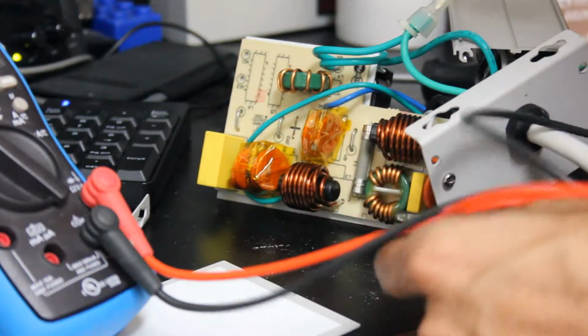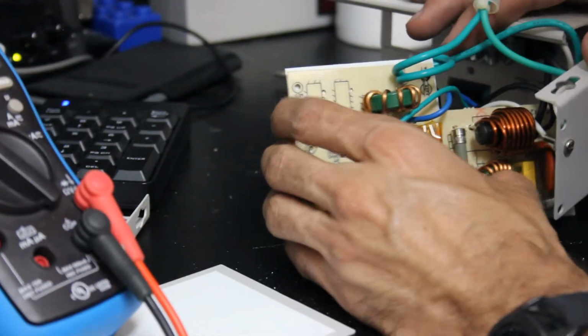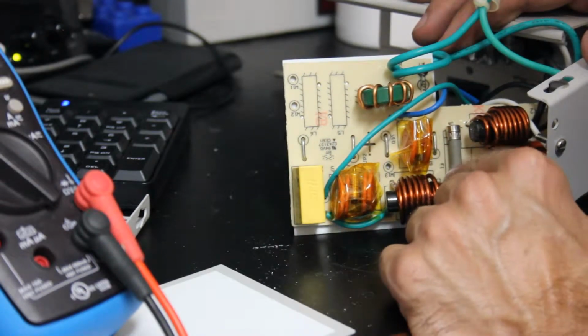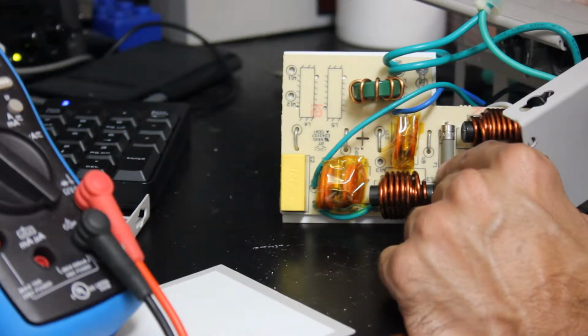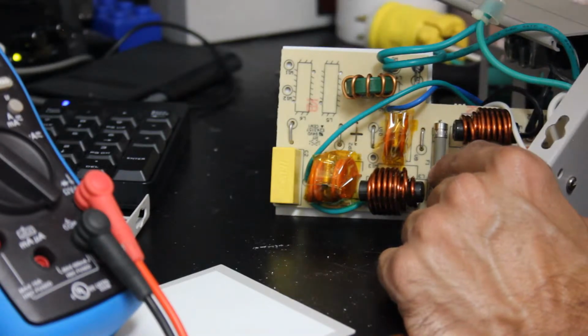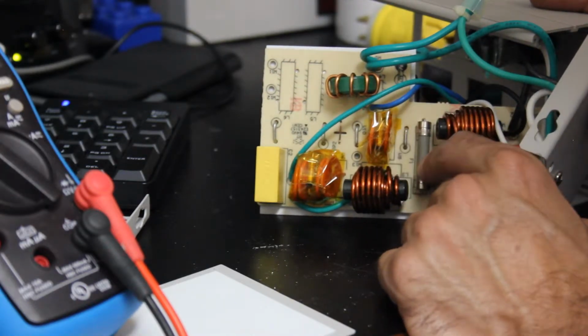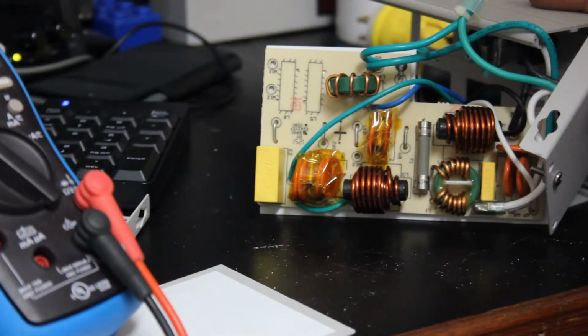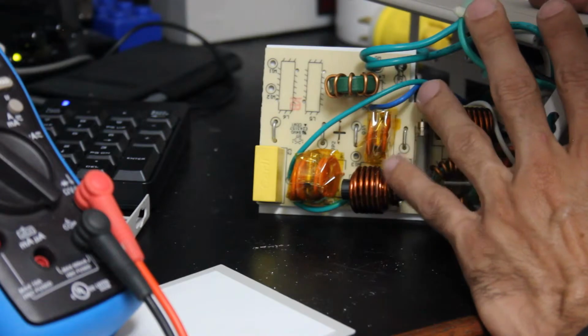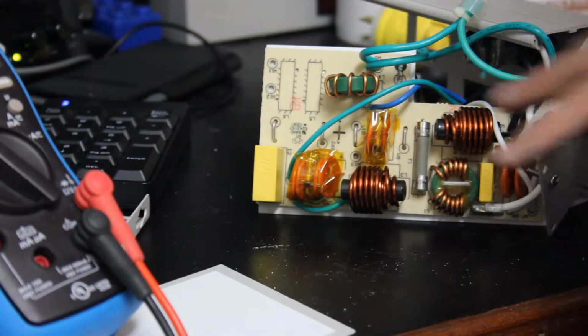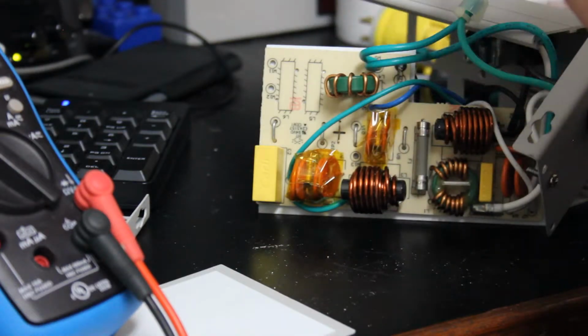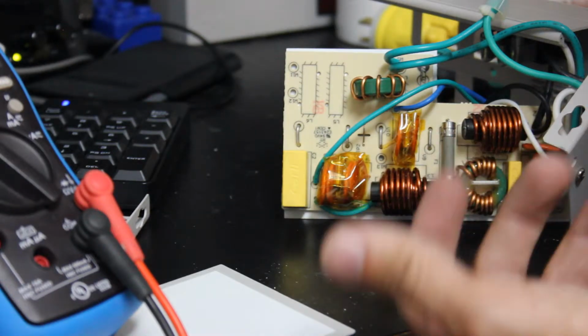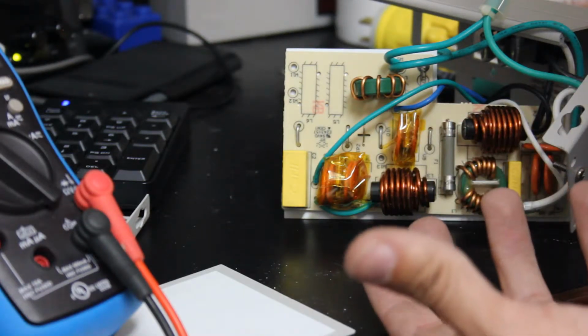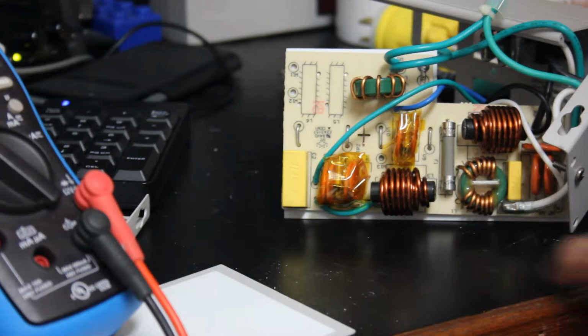So that's very interesting. It wasn't a surge, it was an overcurrent, which, if I think about it, does seem likely. There is a circuit breaker that protects this circuit, specifically the one that this plugs into. It is the only thing fed off of that circuit. So I kind of expected, since the circuit breaker was tripped, that they would have made it so the circuit breaker was the first line of protection rather than the second.